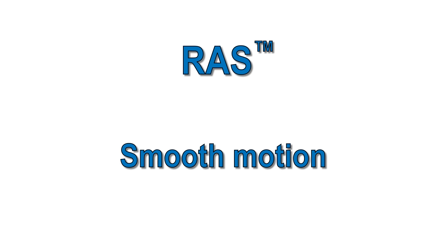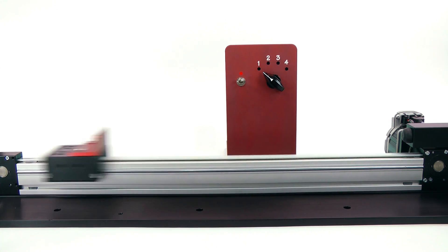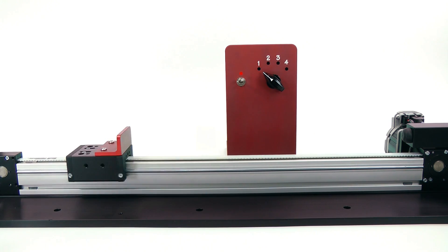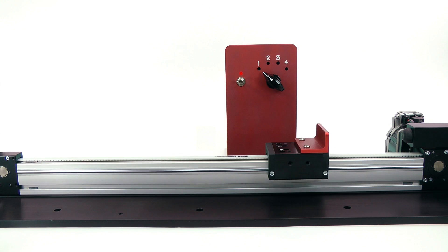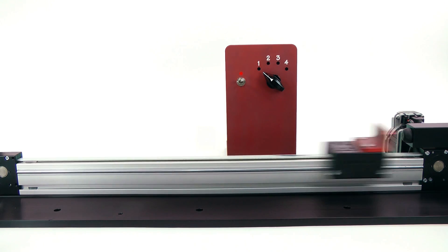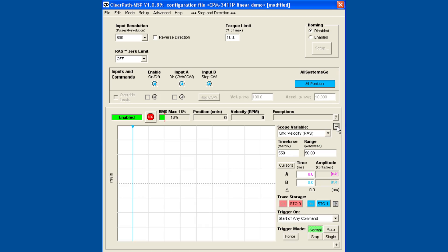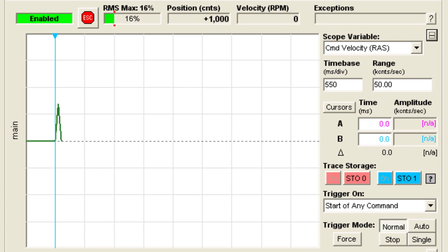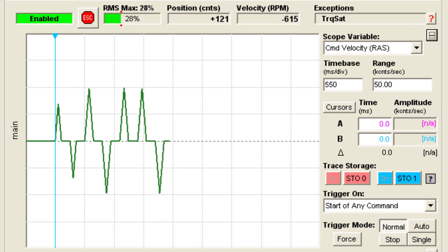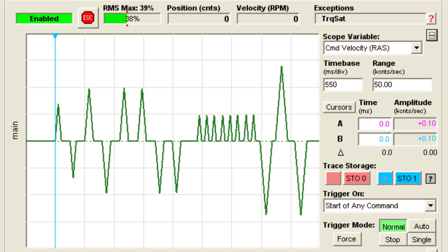Let's take a look at what sort of effect the RAS has. First we'll make a move with the standard trapezoidal move profile. The high acceleration causes some belt slapping and other noise even in this stiff mechanical system. You can see by using the scope function in the MSP software that the motion profile has a trapezoidal or triangular shape.